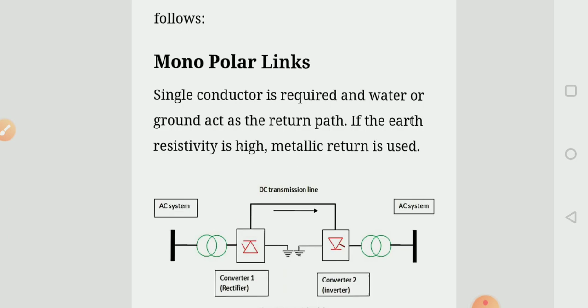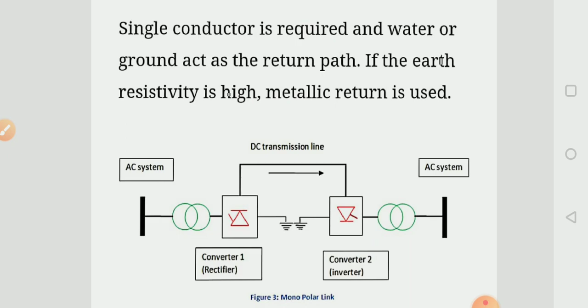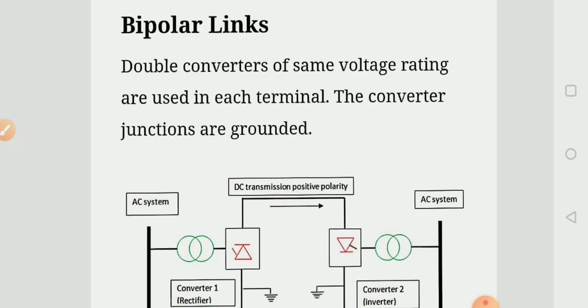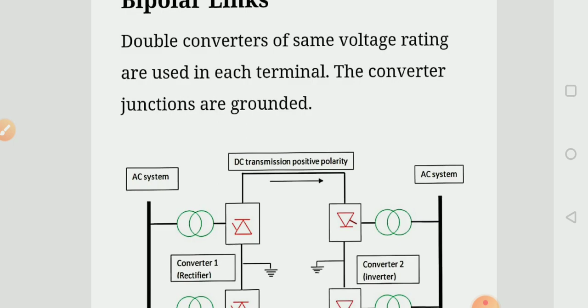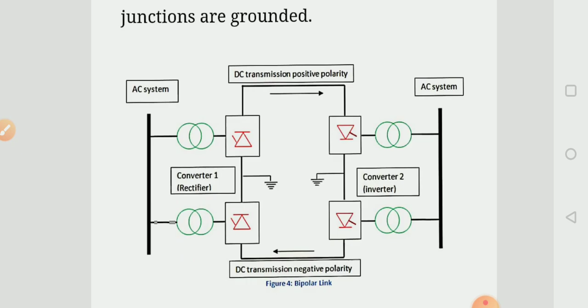Now the classification of HVDC links is as follows. The first link is the monopolar link. Here only a single conductor is required, and water or ground acts as the return path. If the earth resistivity is high, a metallic return is used. Here we use a single converter at the sending end and one converter at the receiving end. Now in the bipolar link we use dual converters, the converter junctions are grounded, and we use dual converters with the same rating.